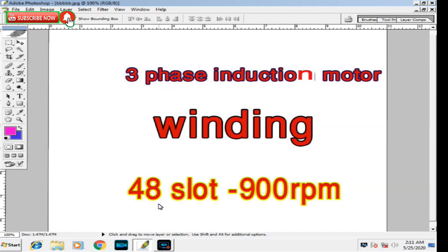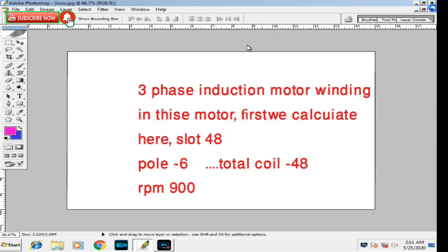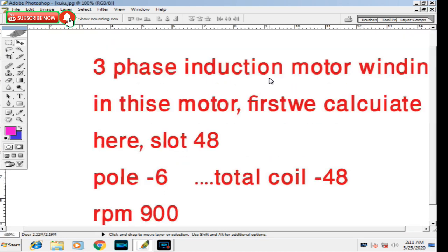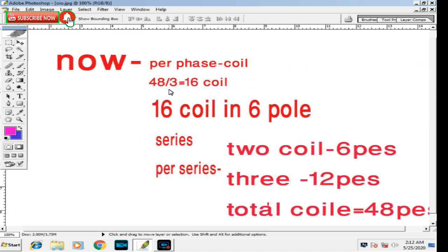3-phase induction motor winding, 48-slot, 900 RPM. In this motor, first we calculate: slot 48, pole 6, total coil 48, RPM 900. Per phase: 48 divided by 3 equals 16 coil.